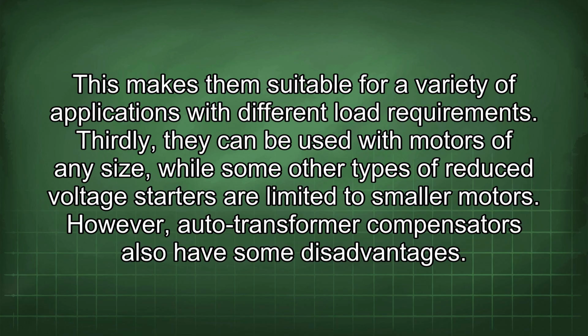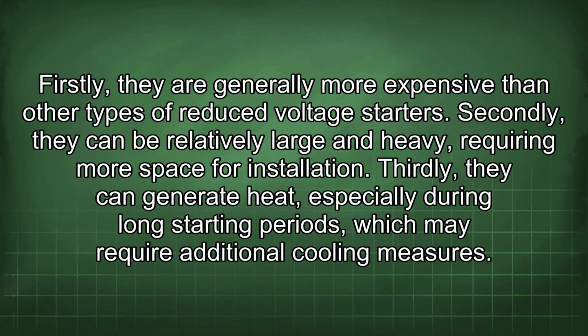Thirdly, they can be used with motors of any size, while some other types of reduced voltage starters are limited to smaller motors. However, autotransformer compensators also have some disadvantages. Firstly, they are generally more expensive than other types of reduced voltage starters. Secondly, they can be relatively large and heavy, requiring more space for installation. Thirdly, they can generate heat, especially during long starting periods, which may require additional cooling measures.